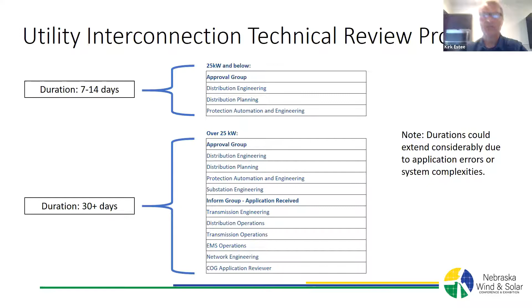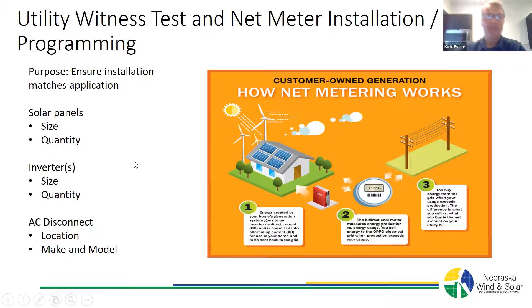The final step in the interconnection process is witness testing. That's where a utility representative comes out at the end and verifies that the quantity and model of solar panels installed match the application, that the proper inverter model and quantity were installed, and confirms the AC disconnect was installed where the application said it would be, with a design sufficient to have visible breaks so grounds can be put on it. That was the final step, the witness test.